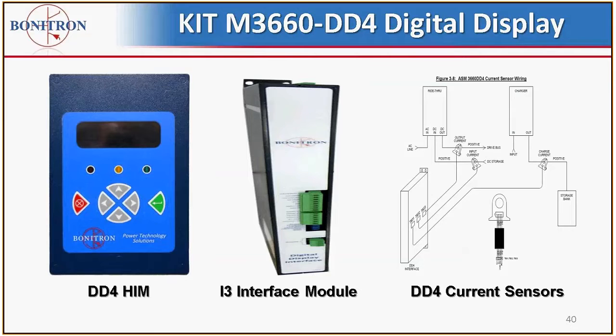Now we're going to discuss the DD4 digital display. This is a very good tool in addition to the indicators we discussed for troubleshooting and system status and ride-through event status. There are 3 parts to the kit. If it's ordered separately, if it's ordered in a system, all these are included in the ride-through system, connected and ready to go to the ride-through units. And the only connections for a cabinet system are to the drive and the AC line in front of the drive. The kit includes the DD4 HIM, or human interface module, the actual display.